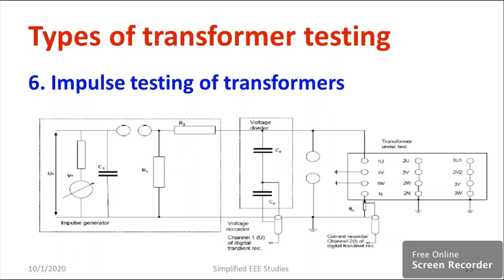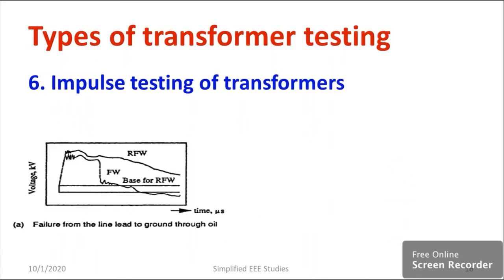You will check the characteristics of the output voltage — whether any serious changes are happening — and make a conclusion. Similarly, you will test all other windings following the same procedure. Based on the different waveforms, you will come to know whether the insulation has certain problems. If you observe these kinds of waveforms, we will know that this is a failure from the line lead to ground through the transformer oil.